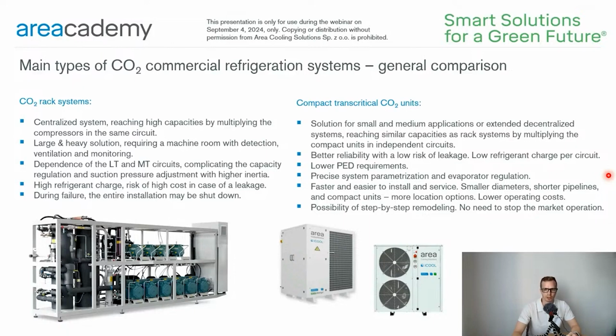Installation with compact transcritical CO2 units enables more precise parametrization and evaporator regulation. The commissioning and service is faster and easier. We also have more location options because pipeline diameters are smaller, circuits are shorter, and the units are compact. And of course, there is a possibility of step-by-step remodeling. No need to stop the business operation. The conclusion is that both solutions are good, but compact units combined with the concept of decentralization of the system ultimately bring greater reliability, flexibility, and cost savings.